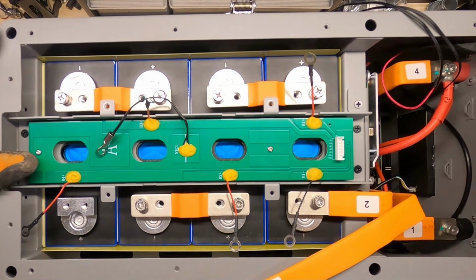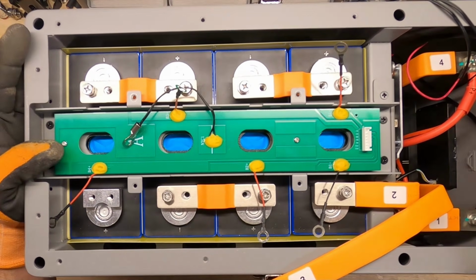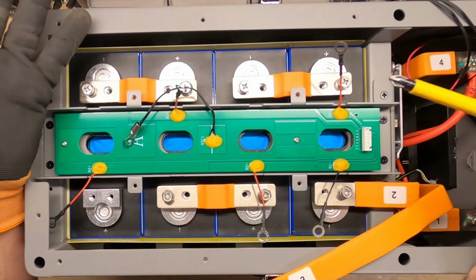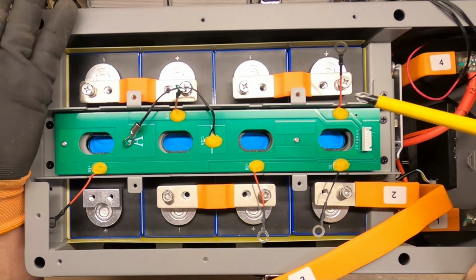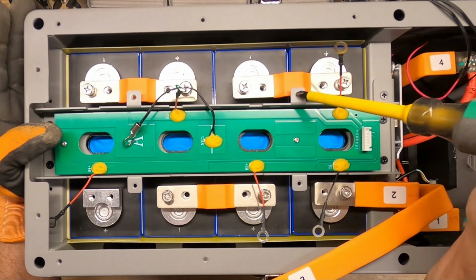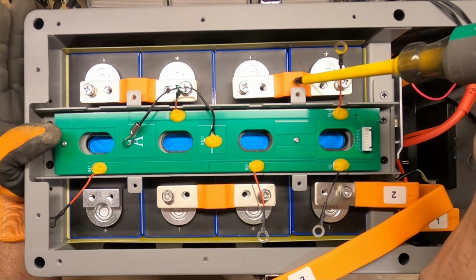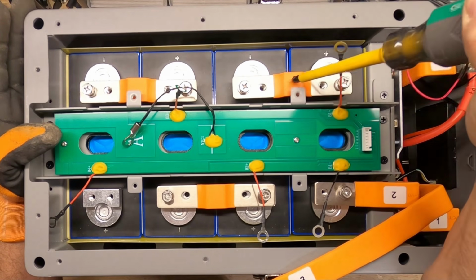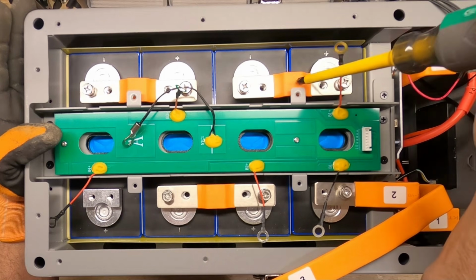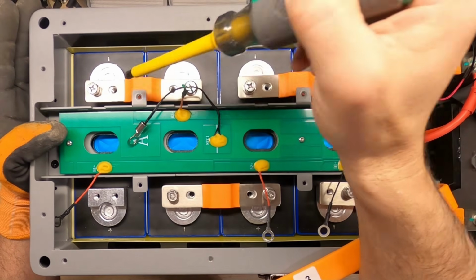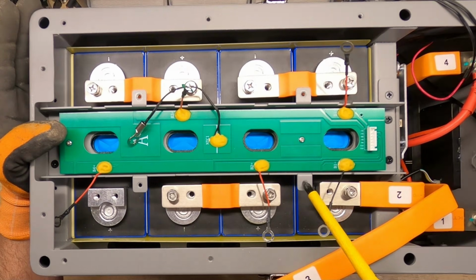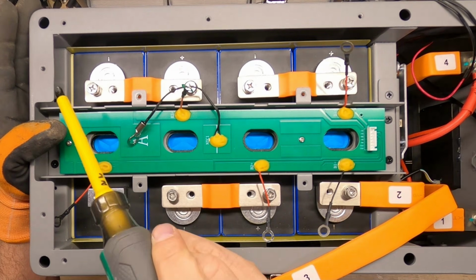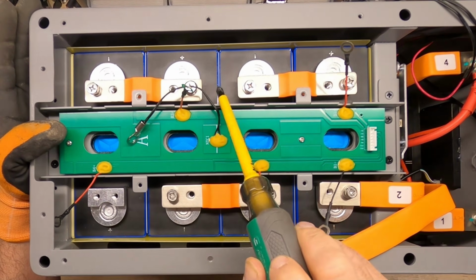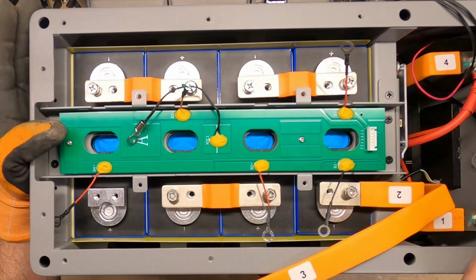Perfect. Oh my God. Again, what is up with this? Both on the 24-volt and now the 12-volt kit, the mounting tab with the screw is directly over the bus bar. If the screw goes through here and penetrates this insulation, it will cause a short. Again here. These two are okay. These tabs need to be here, here, not over the bus bars.